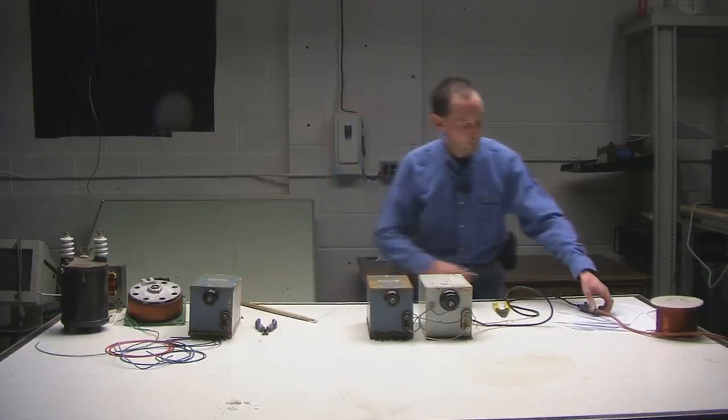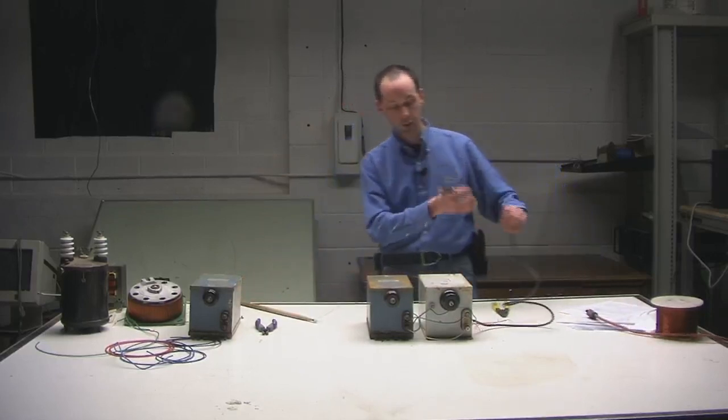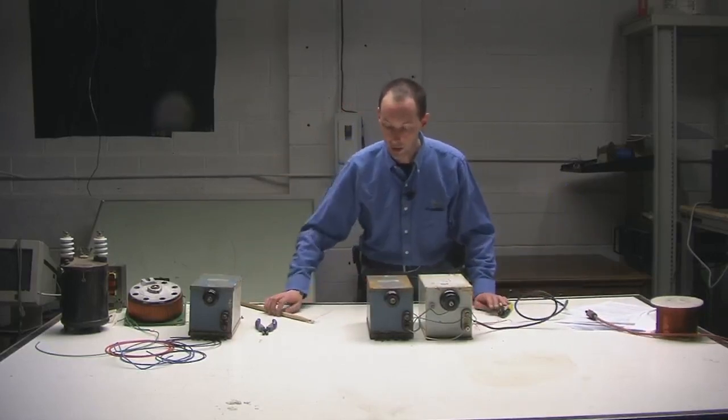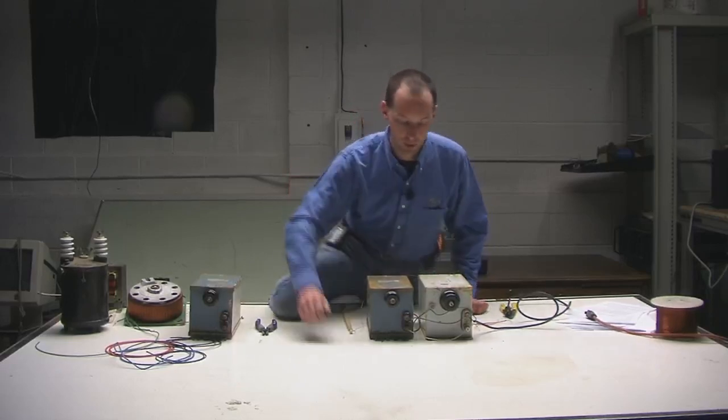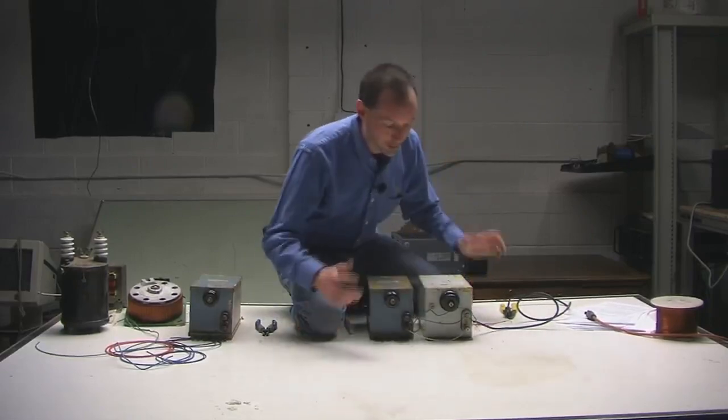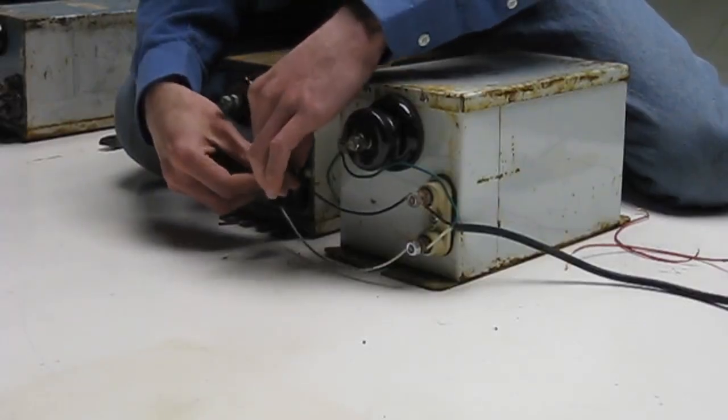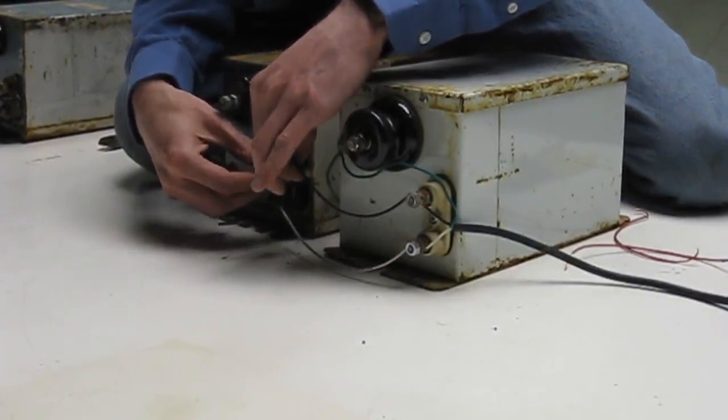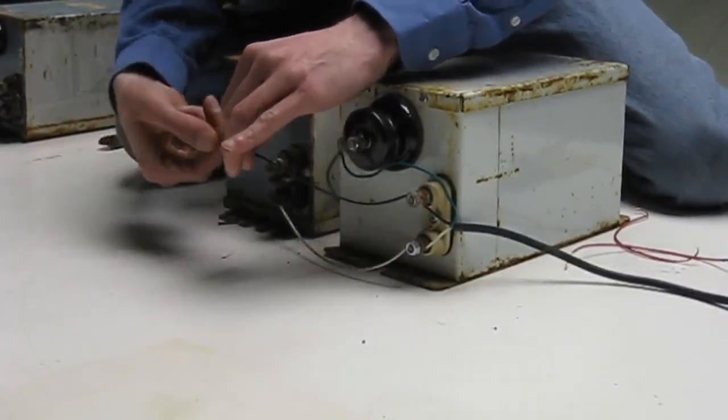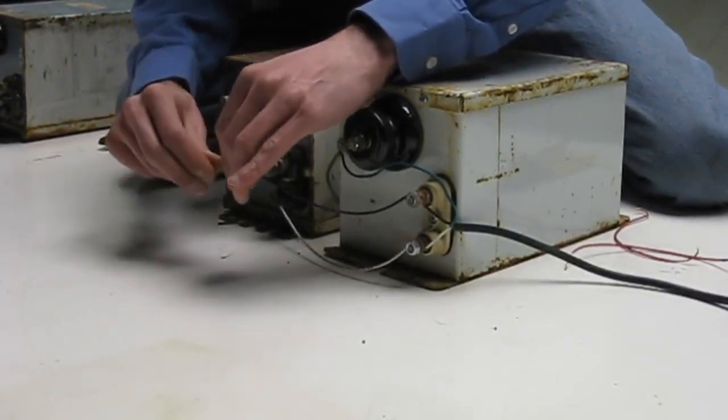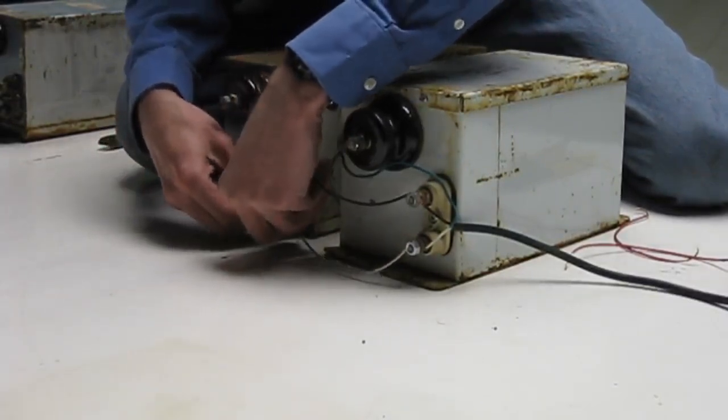So we unplug. There's the plug. So we know we're safe. And now here's the super high-tech secret of how to phase NSTs. Because now you've tested them, and you've found out they're out of phase. So you disconnect the wire, and clean it off, because it's all manky now that you crushed it in the screw. And you disconnect the bottom wire.